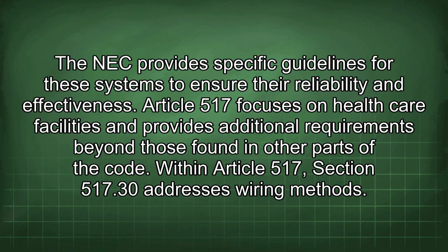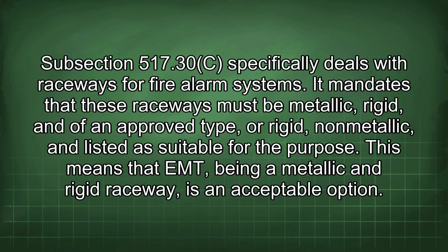Article 517 focuses on healthcare facilities and provides additional requirements beyond those found in other parts of the Code. Within Article 517, Section 517.30 addresses wiring methods. Subsection 517.30c specifically deals with raceways for fire alarm systems. It mandates that these raceways must be metallic, rigid, and of an approved type, or rigid, non-metallic, and listed as suitable for the purpose. This means that EMT, being a metallic and rigid raceway, is an acceptable option.